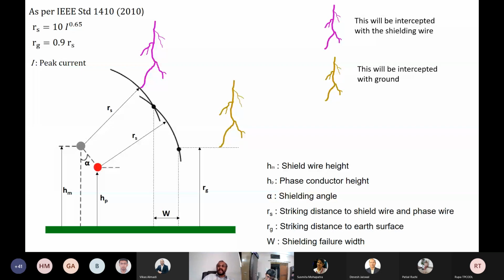And if the lightning, like the yellow color lightning, comes from away from these rolling imaginary spheres, then it will definitely intercept with ground. So in both cases, there is no problem for the live wire. But the problem is if the lightning comes from there, the red color one, because now it is getting attracted or getting attached to the live wire rather than to ground or to the shielding wire.